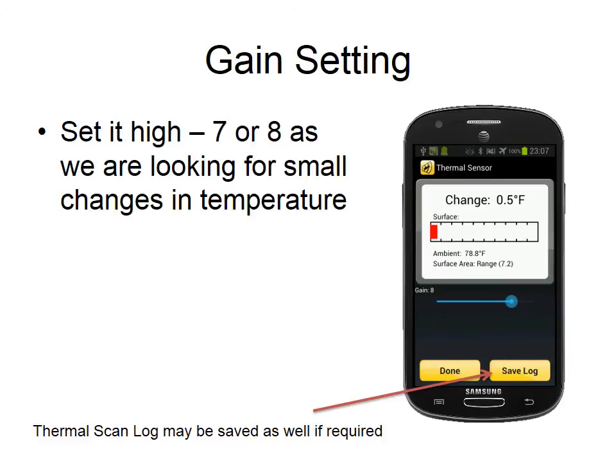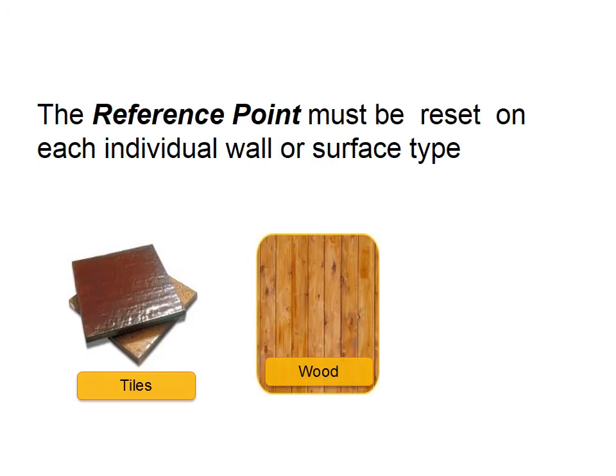The gain setting on the thermal sensor is recommended to be run at 7 or 8. This allows for detecting small variances in temperature. A thermal scan log may also be saved if required by hitting the Save Log button, and then it's the same as the other two sensors. The reference point must be reset on each surface, as each surface type retains its own heat signature. This heat signature is also affected by the temperature of the day.